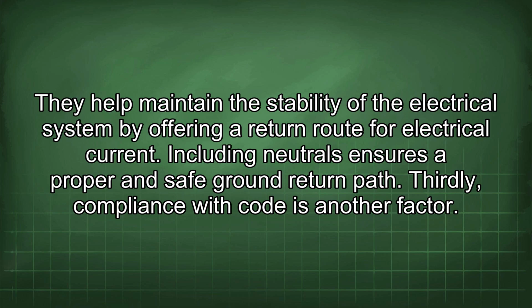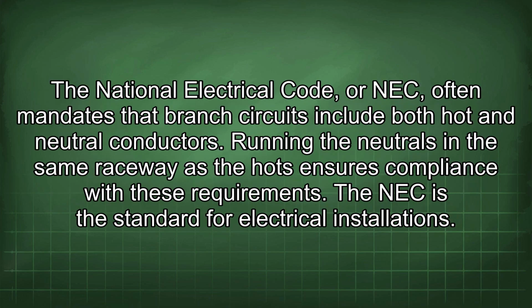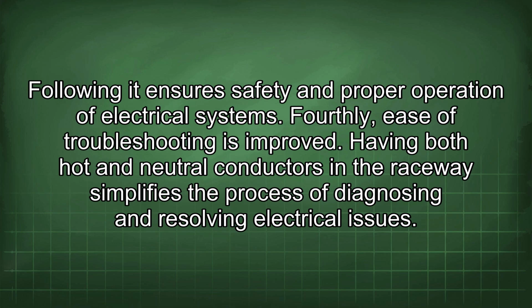Thirdly, compliance with code is another factor. The National Electrical Code, or NEC, often mandates that branch circuits include both hot and neutral conductors. Running the neutrals in the same raceway as the hots ensures compliance with these requirements. The NEC is the standard for electrical installations. Following it ensures safety and proper operation of electrical systems.